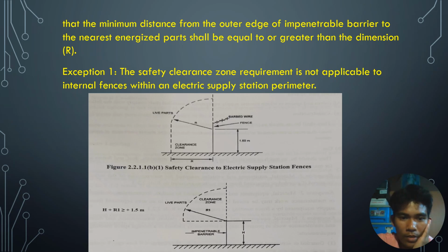So as you can see, there is the clearance zone, the distance from the live parts to the wall or barbed wire or fence, and the limit of height of the fence is 1.5 meters.